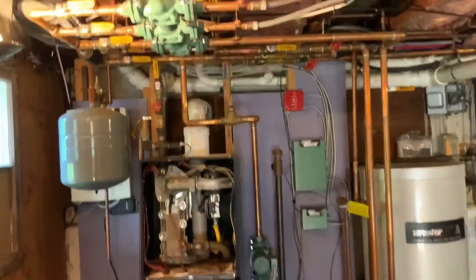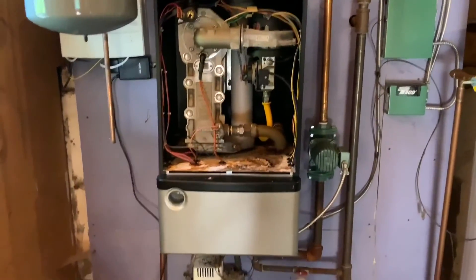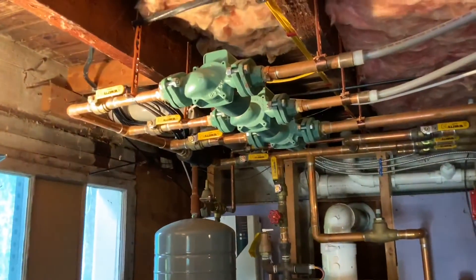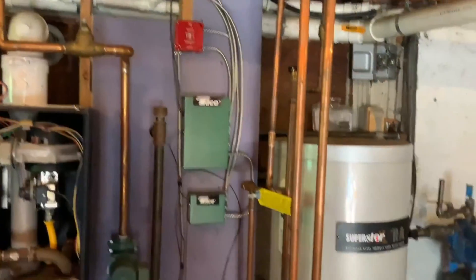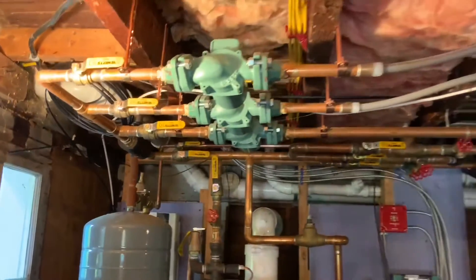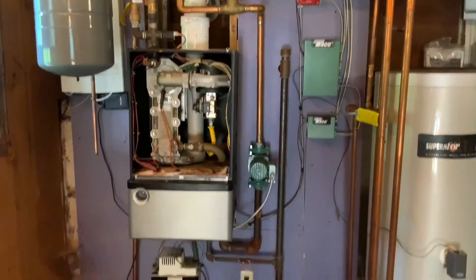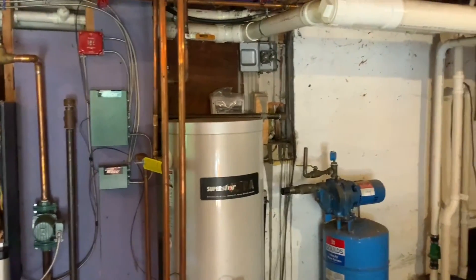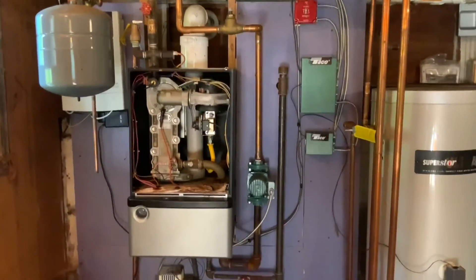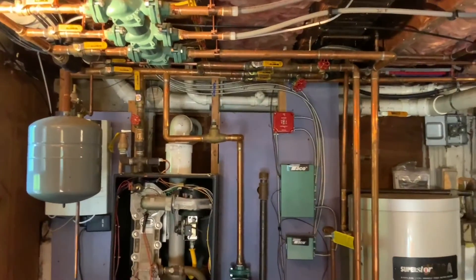Today we're in Chelmsford, Massachusetts where we have an 11-year-old Burnham boiler that has failed and a leaky SuperStor. We're going to remove all of this failed equipment, put a new piece of plywood on that back wall, re-pipe everything, and install a Lochinvar Noble combination unit which will deliver all the hot water and supply all the heat needed for this home.